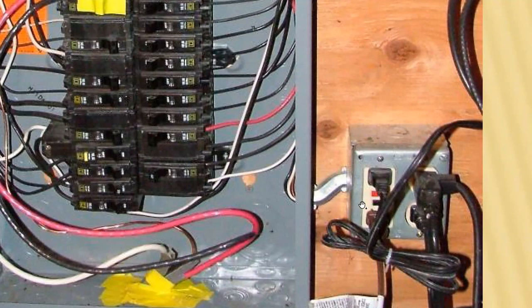And the resistance of the box is pretty much zero. So you're going to have a huge current flowing through that wire, which is going to be way more than the circuit breaker allows, because that's a safety measure. Let's say the circuit breaker is specified as 15 amps. If there is anything more than 15 amps flowing through that circuit breaker, the circuit breaker is going to go, oh, nope. Poof, it's going to open, interrupt the circuit. Too much, right? You're trying to carry too much through that wire. So of course, if that hot wire touches the box and the current flows directly to the ground, it's going to be a huge amount of current, way more than this can give you, and the circuit breaker is going to trip and open the circuit.